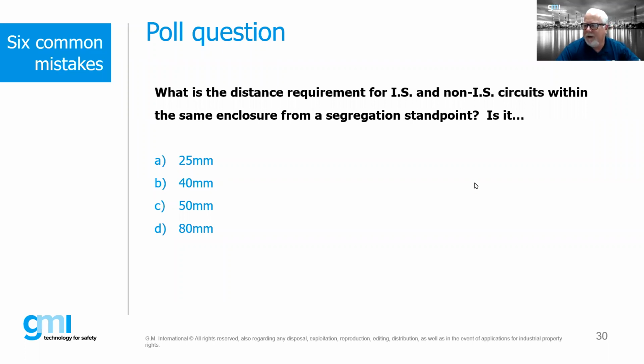There's a question: what is the best recommendation when it comes to shielding to save space and cost? Metal shields have been used to avoid extra trunking - is this an acceptable solution per the standard? There are different ways of doing shielding. You could use shielded cables to save space inside your panels, or use partitions as I mentioned, so that the 50 millimeter distance gets shrunk down if we go up 25 millimeters and down 25 millimeters. There are many different ways to address it - there's not necessarily one perfect way, but shielding and separation are both acceptable.